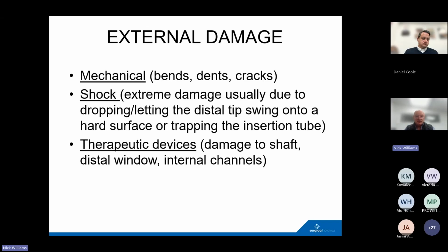Internal, and to a certain extent external as well, is damage from therapeutic devices. If you've got a lithotripter at the tip moving around, that can damage the tip of the scope. With lasers, there are lots of cases where lasers have been fired internally by mistake, and that obviously blows a hole in the channel.